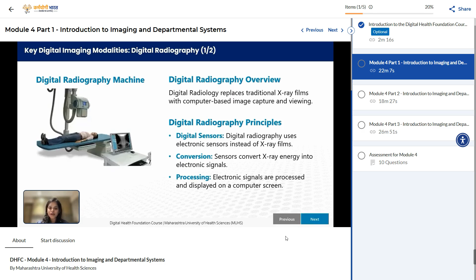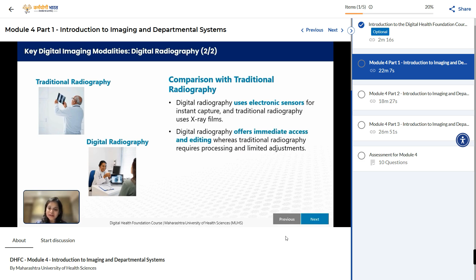So this is what digital radiography is like. The film has now been replaced by a system where we see the image on a monitor. To recapitulate, digital radiography uses electronic sensors for instant capture, and traditional radiography uses X-ray films. Digital radiography offers immediate access and editing, whereas traditional radiography requires processing and allows limited adjustments. Digital radiography provides superior image quality, streamlined workflow, and low radiation exposure compared to traditional methods.